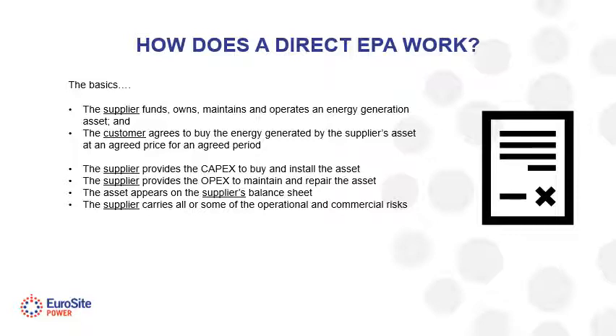For example, with a combined heat and power unit, one of the key commercial risks is known as spark spread. This is the difference in the cost price of the gas that fuels the machine and the electricity that's generated by the machine. If that spread between those two prices narrows, then the saving that's delivered to you as the end user reduces. If you own that piece of equipment, then you're carrying that risk.